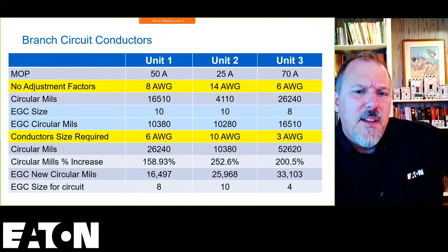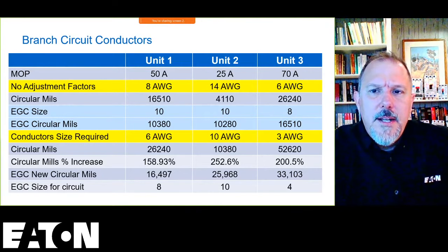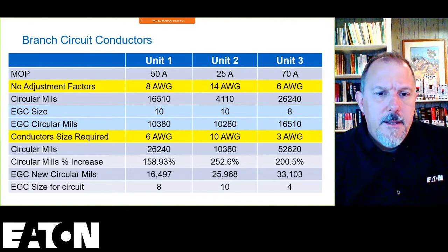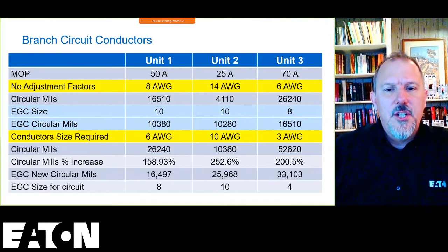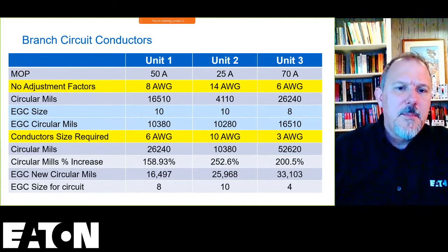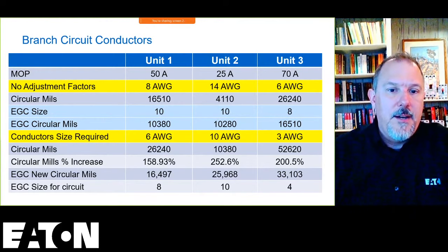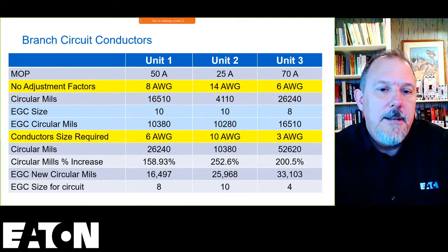I've got my 50, 25, and 70 with no adjustment factors, etc. So I've got my minimum circuit ampacities. Hold on here. So those are my numbers. I did my circular mills and the increase. So I show you the size based upon all of the numbers, and you understand hopefully where we get all those numbers now.